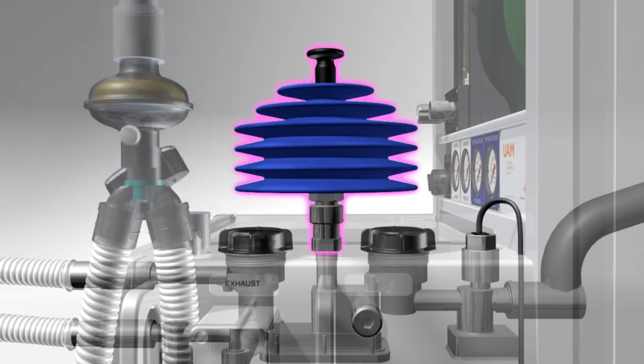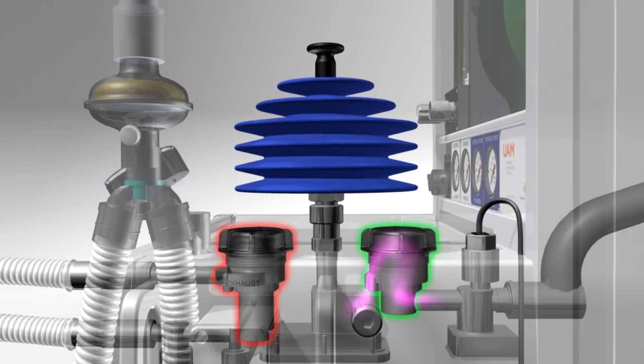The second is draw-over vaporizers. The draw-over vaporizer is driven by negative pressure developed by the patient and must therefore have a low resistance to gas flow. Its performance depends on the minute volume of the patient.